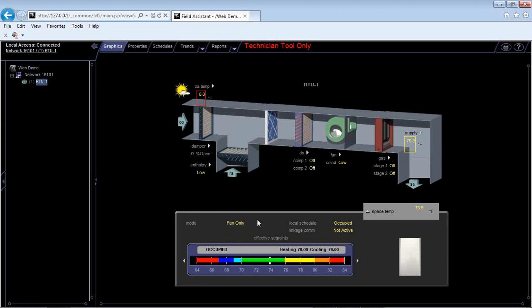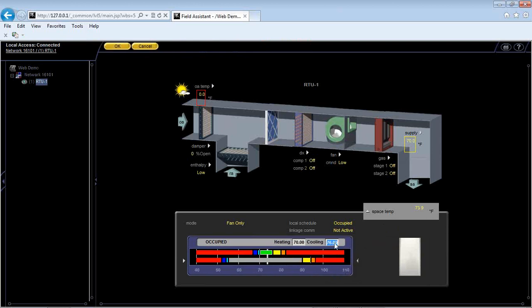Now because I'm occupied, I'm going into fan only. So my fan's going to turn on and I'm maintaining my set points. So if I wanted to test the unit now, I have all these values coming in. Let's say I wanted the heat to turn on. Well, right now I'm at 74 degrees in the space. I don't need any heat, right? I'm at 70 degrees heating set point, 76 cooling. If I hit this arrow, I can move my set points so that I fake the heating on. So if I go to 85 cooling and 77 heating, I need to make sure I maintain my minimum set point separation. I hit OK.